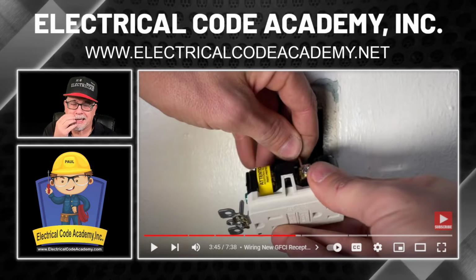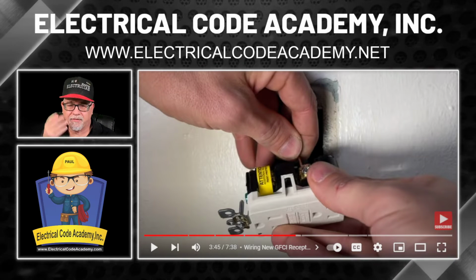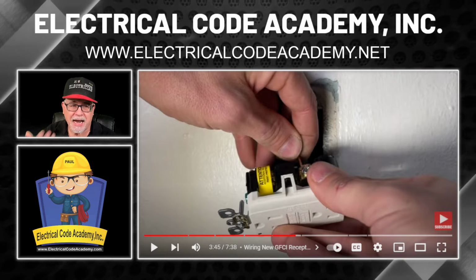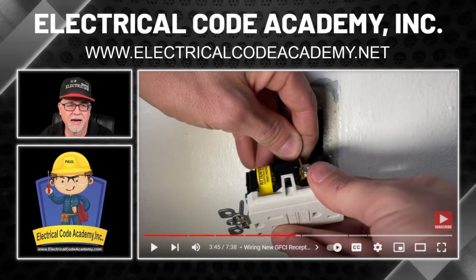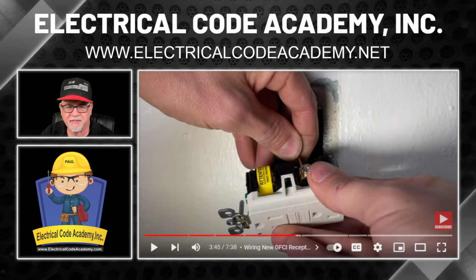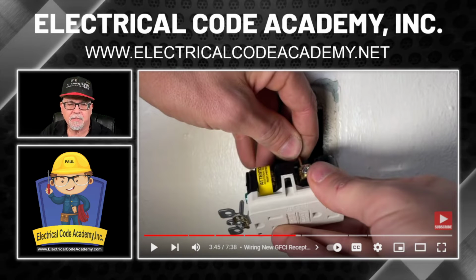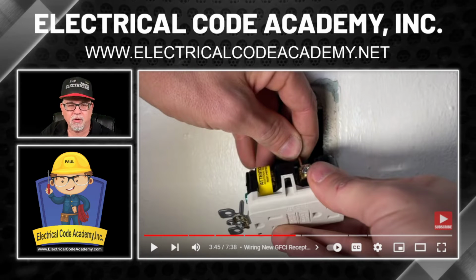Now, whether you like it or not, some of these devices will have this. Some of them will have a back wire, because 15 amp typically have a back wire. You won't get a back wire on 20 amp. I see this looks like a 15 amp GFCI because it doesn't have any T slot on the neutral side.